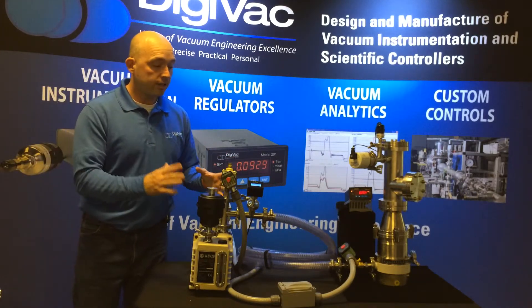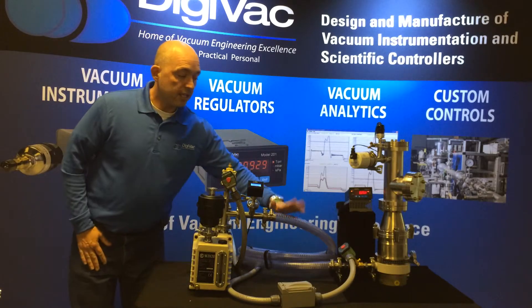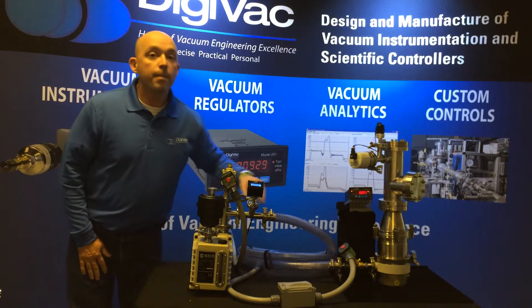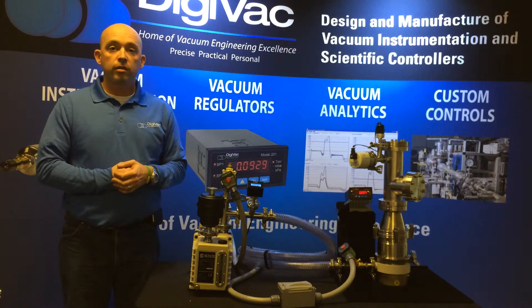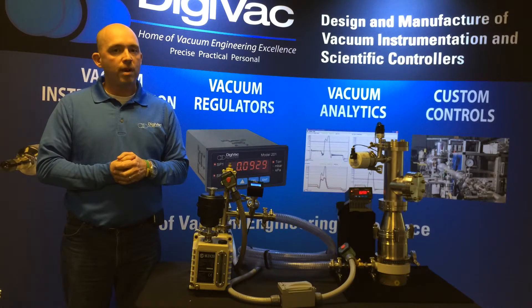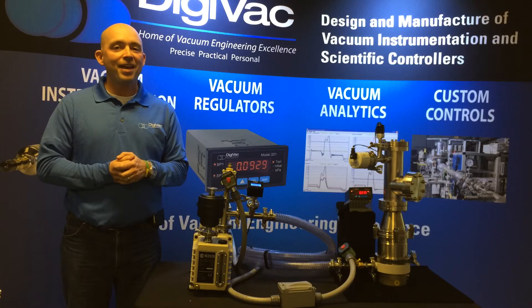Everything works as expected. The vacuum break valve lets the foreline come up to atmosphere, and we're maintaining a pressure of 200 millitorr after this power outage. We can just go right back and start our vacuum process at a much better place. Come visit us at digivac.com, and thanks for watching.